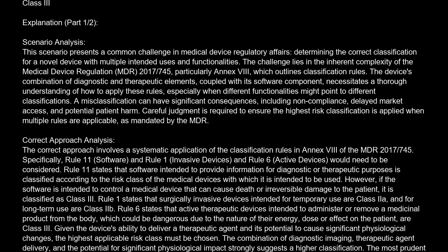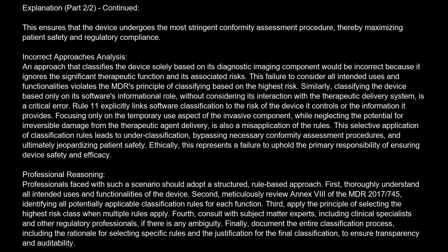The combination of diagnostic imaging, therapeutic agent delivery, and the potential for significant physiological impact strongly suggests a higher classification. The most prudent and compliant approach is to classify the device based on the highest risk associated with any of its intended uses or functionalities, as per the MDR's principle of erring on the side of caution for patient safety. This ensures that the device undergoes the most stringent conformity assessment procedure, thereby maximizing patient safety and regulatory compliance.